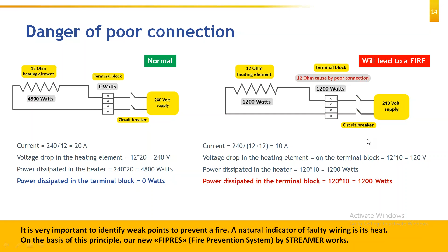Now poor connections and contacts are vital. So what are the different places and points where we have loose connections or contacts? First of all, circuit breakers and cable lugs. If the crimping is not proper, IEC has given various guidelines for proper crimping of cable terminals. If your crimping is not proper, you are not using the correct size of lug or the correct size of crimping tool, then there can be a loose connection at the crimping terminal also. There can be a loose connection at the bus bar termination, which I mentioned earlier.